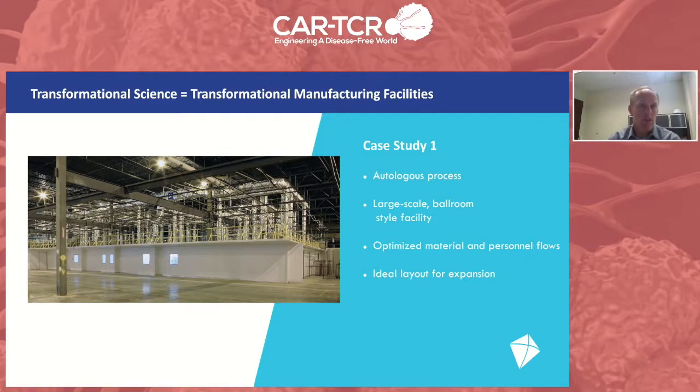We used large-scale industrial HVAC systems to serve this cleanroom core, including some non-recirculating airstreams, redundancy features, and segregation to protect against cross-contamination of products within the facility. The ability for future expansion was built into the design from the very beginning. This photo shows the original clinical pilot plant that was developed with dedicated adjacent space to accommodate a future expansion, which we performed three years later when the demand for this product increased dramatically. We included in that original project an extension of the modular walkable ceilings so that we could easily accommodate the installation activities of the expansion project—which occurred at the same time that the pilot plant remained producing product only two inches away. The two plants were then joined together over a brief weekend shutdown into one expanded facility.